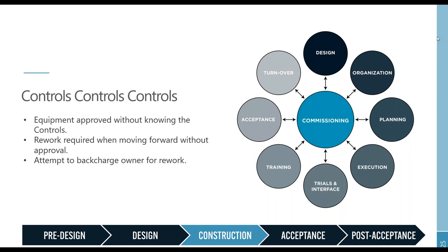In this case, because they had moved ahead and hadn't documented what they were doing before they were actually putting it out into the field, we hit a point where things started having to get ripped out, because what they had put in was not going to work for the equipment that was being installed. It didn't match the design documents and it wasn't going to be a workable system for the owner to be able to operate and maintain.